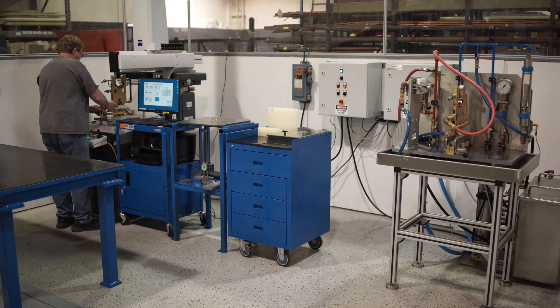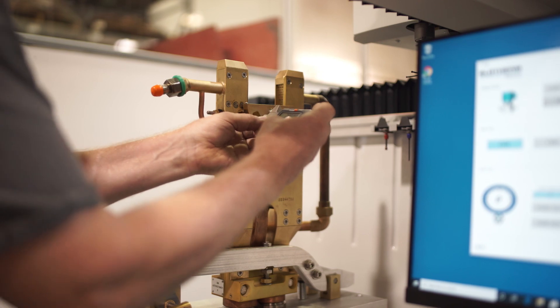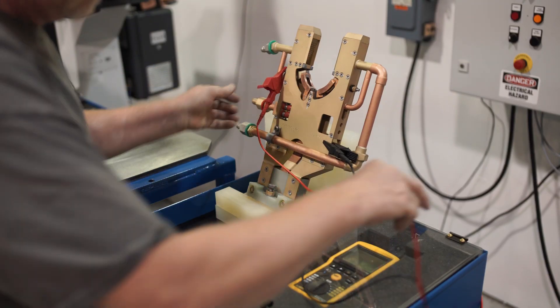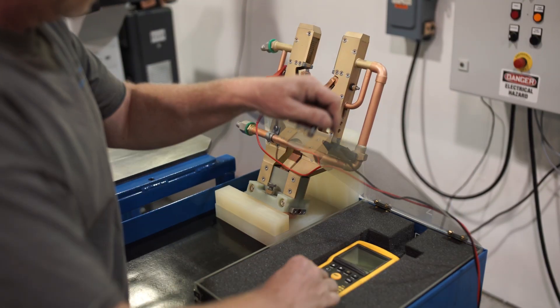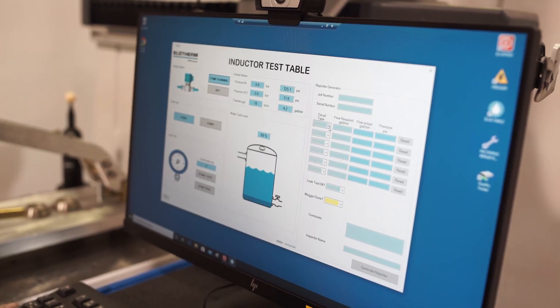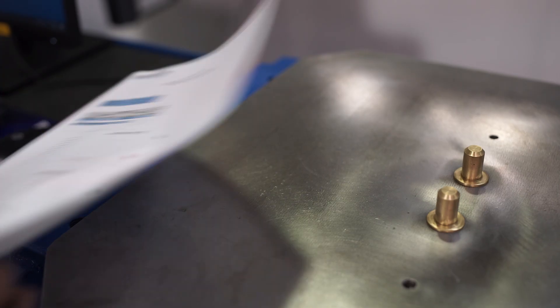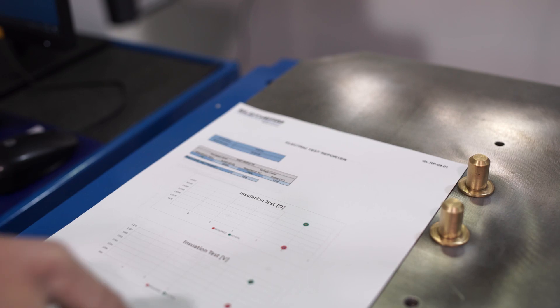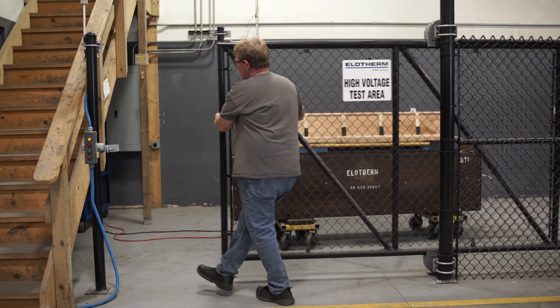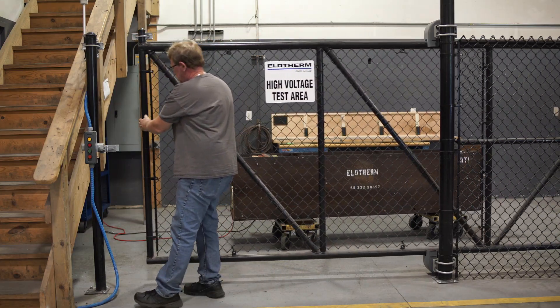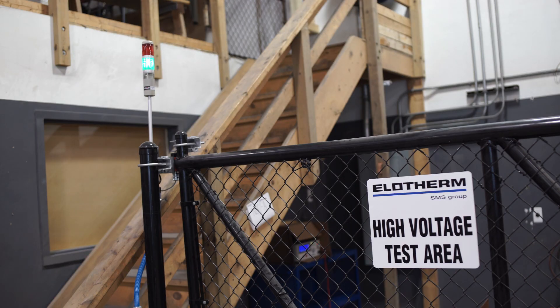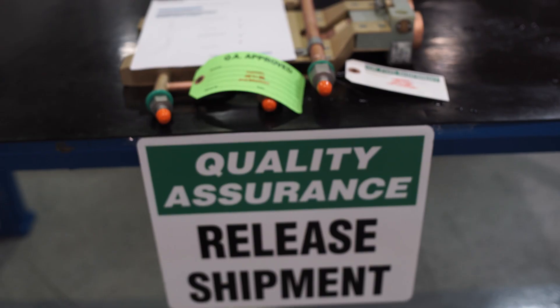All of our hardening inductors are tested to meet the highest standards. Hypot tests ensure the inductor's insulation is working perfectly. Pressure tests guarantee there are no leaks. A final report is generated, and our inductors undergo a high-voltage test for arcing. The robust system shows us a perfect inductor.